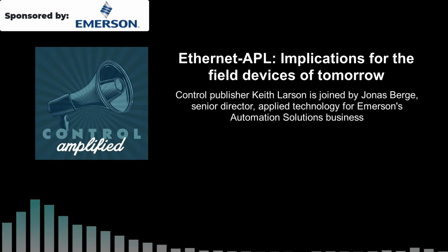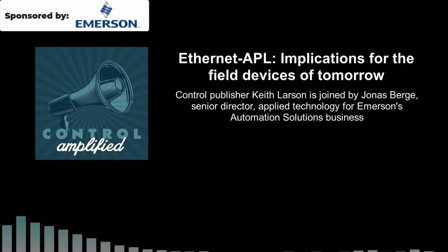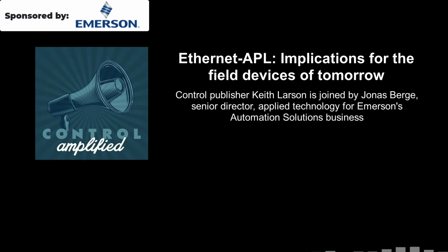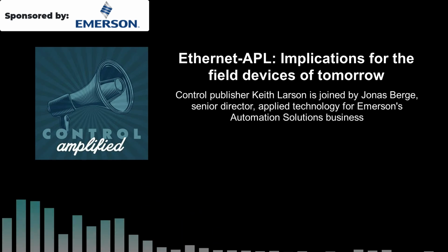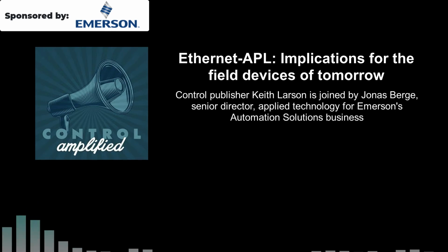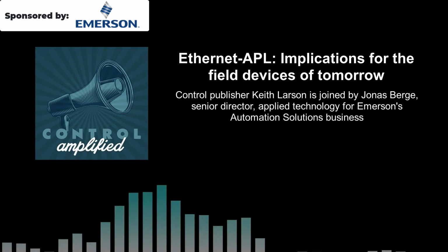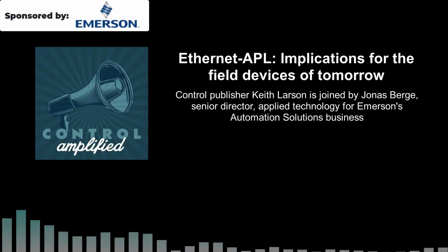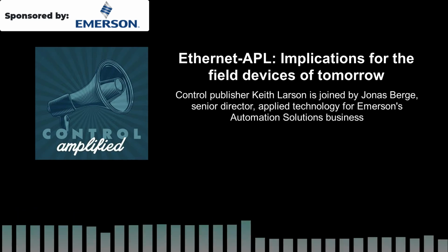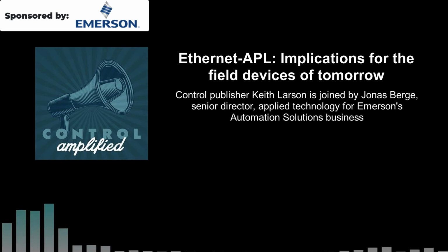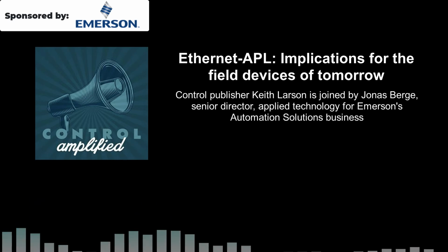Well, there's plenty of bandwidth. Ethernet-APL supports IP, and with that it enables multiple application protocols. So with APL, it's no longer HART or Modbus or Profibus—it's really HART-IP, Modbus TCP, and Profinet, plus other protocols such as HTTPS for web browsing or RTSP for video, all on the same wire at the same time. There will also be OPC UA to HMI panels and analyzers.